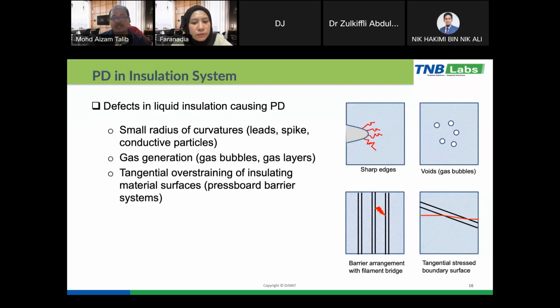In this slide, I will share what the causes of partial discharge are in liquid, solid, and also in gas. Normally, the design of the equipment is based on these three materials. Either we use liquid insulation, solid insulation, or gas insulation. Sometimes there is a combination of liquid and solid. For example, in the power transformer, we use oil insulation and paper insulation as liquid and solid insulation. In the cable, we use only solid insulation, but sometimes we have oil-filled power cable, where we use liquid and solid. For GIS, normally the insulation is only gas.